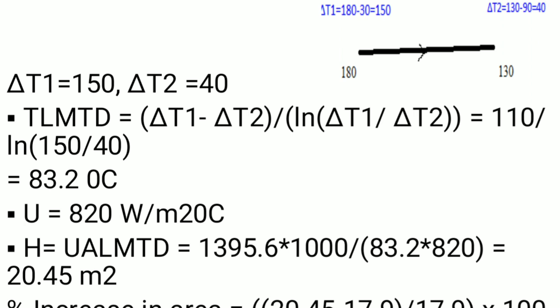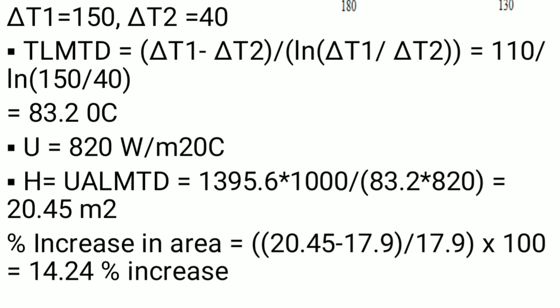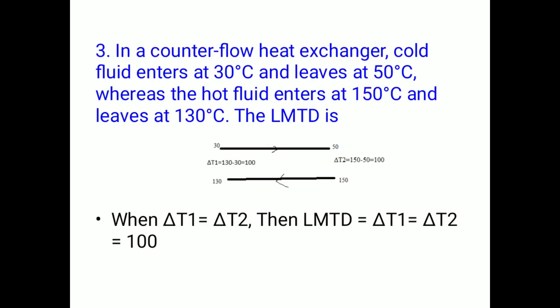With parallel flow LMTD = 83.2°C and the same Q and U, the required area is 20.45 m². The percentage increase in area = (20.45 − 17.9) / 17.9 × 100 = 14.24%. This shows that counter-flow exchangers require less area than parallel-flow for the same duty.